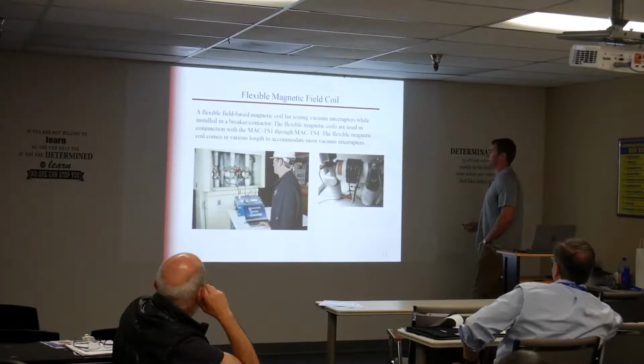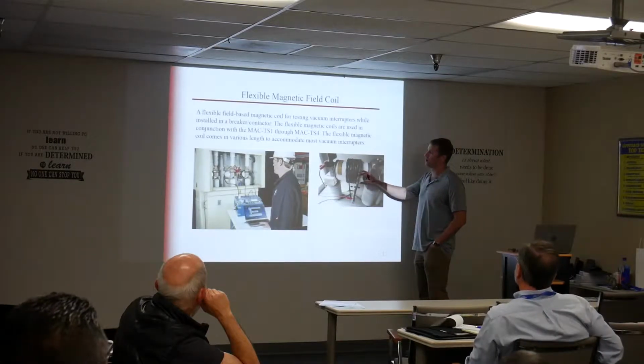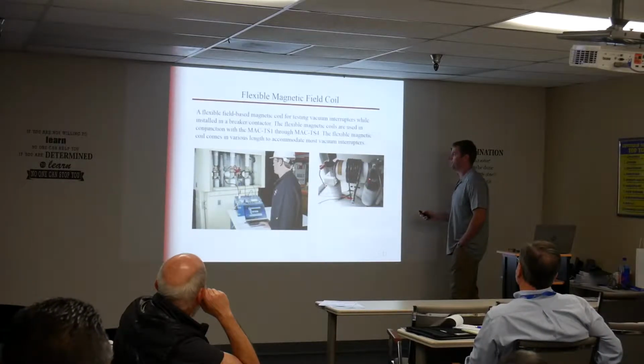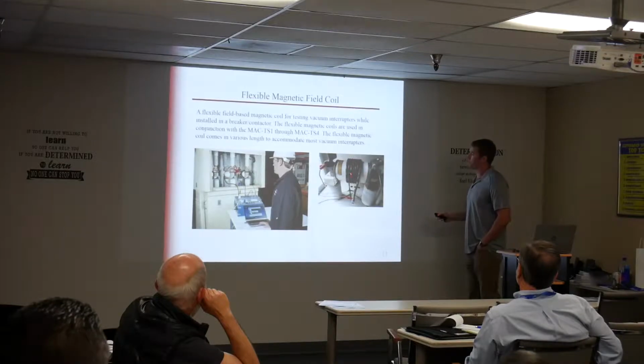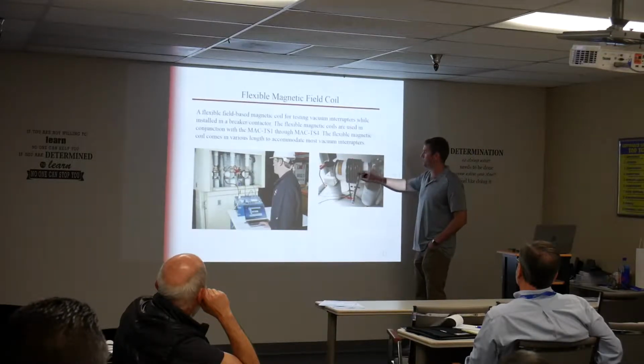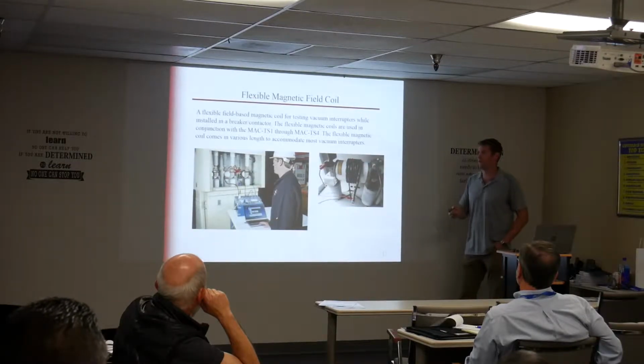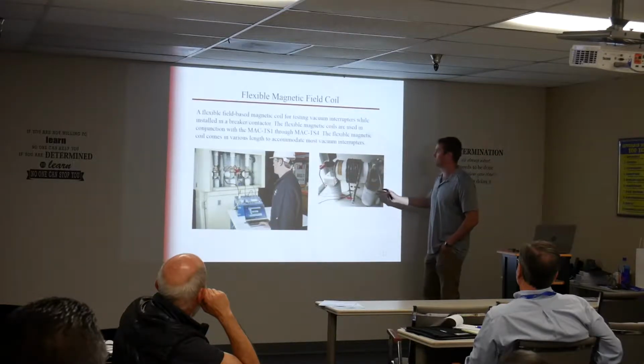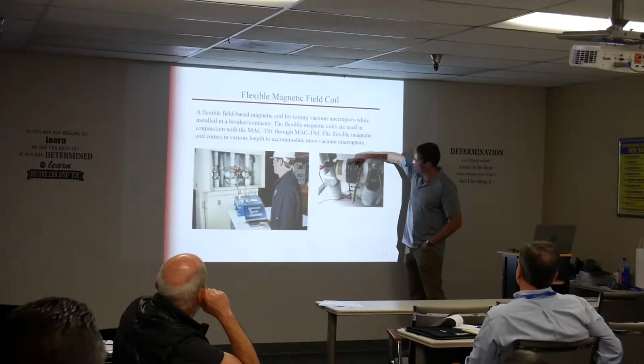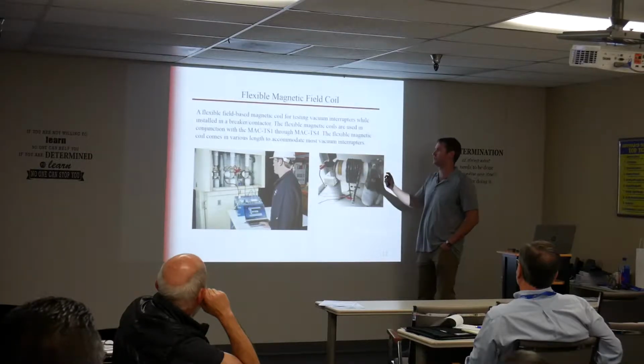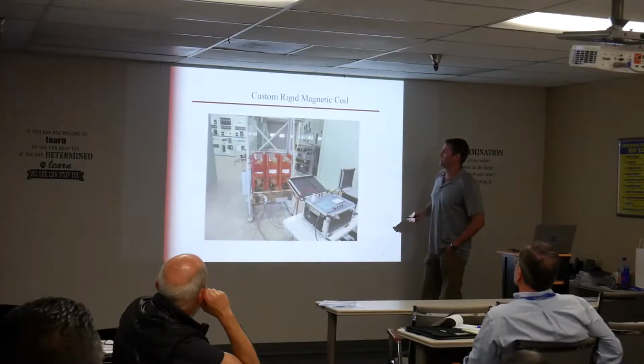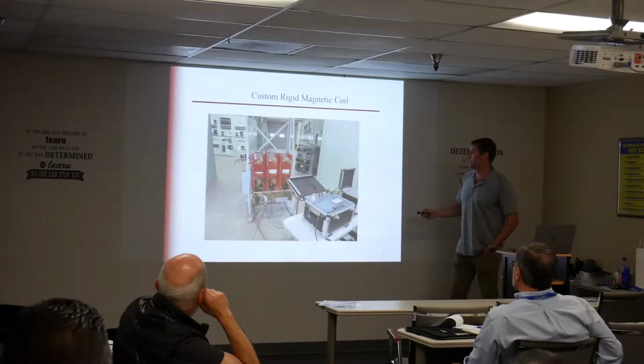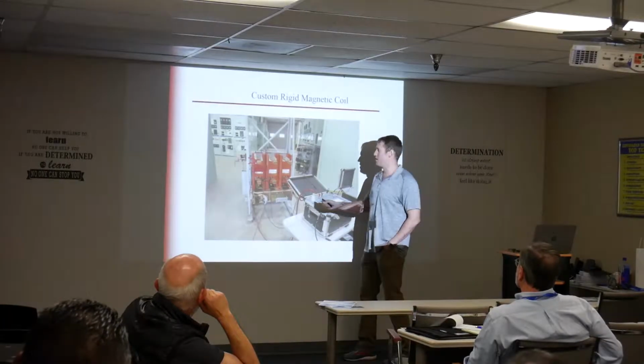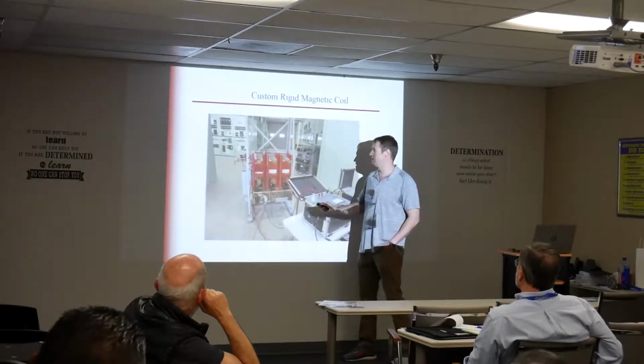But really, how do you apply a magnetic field to a bottle installed in a breaker? Really this is what we came up with, this flexible magnetic field cable. And in this cable is a bundle of 50 smaller wires. Applying a magnetic field is just passing current or voltage through a wire. So you have to wrap it 5 times around the center of the bottle to saturate the magnetic field. And then you have your high voltage and signal return. So that's how the test setup looks. But then there's also a couple of breakers where you don't have access to the bottles, like the GE PowerVac.